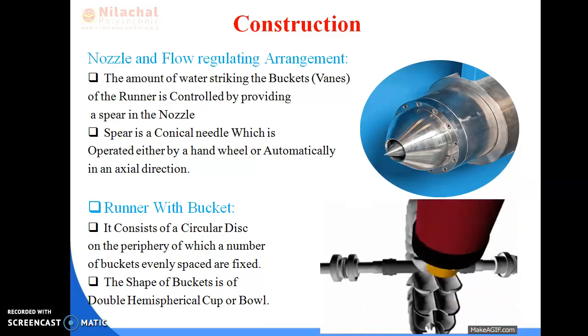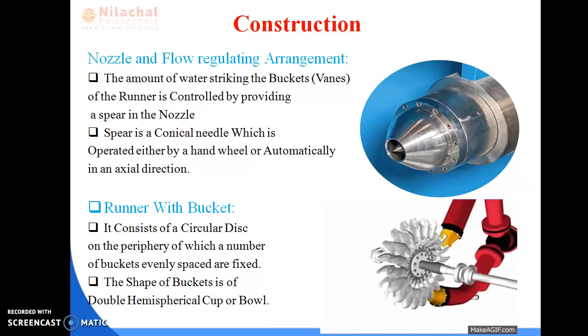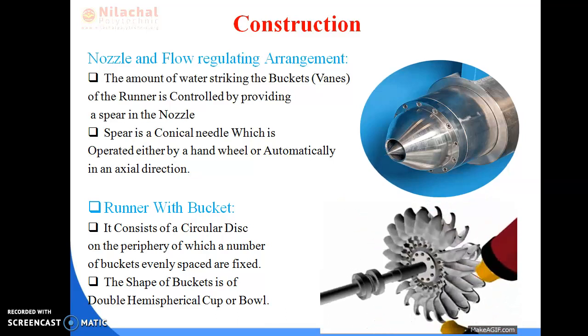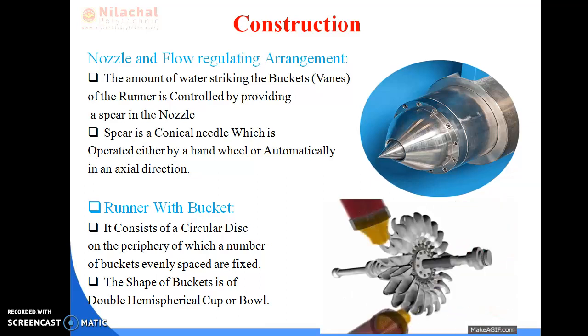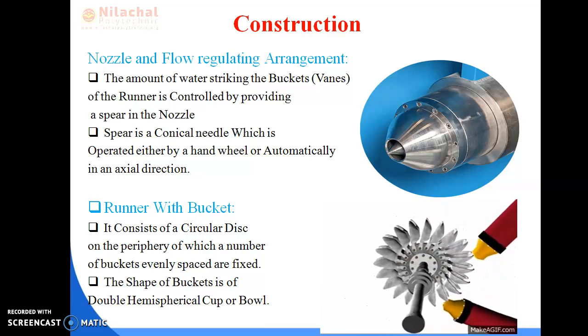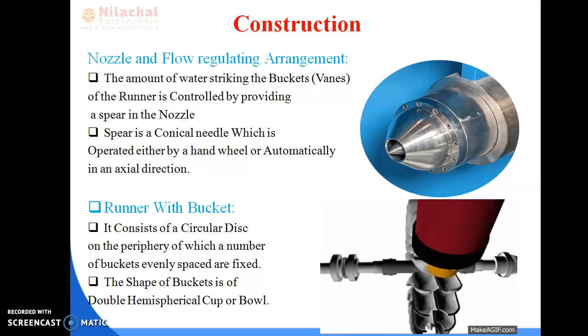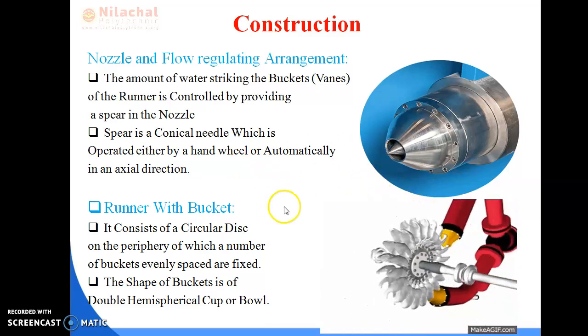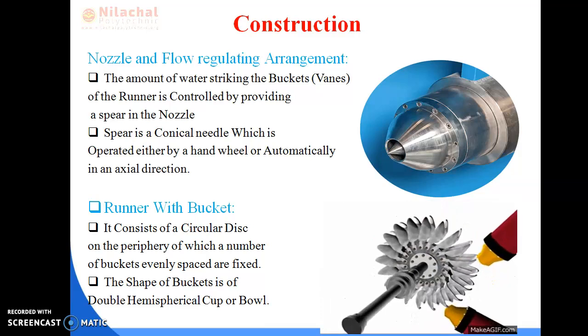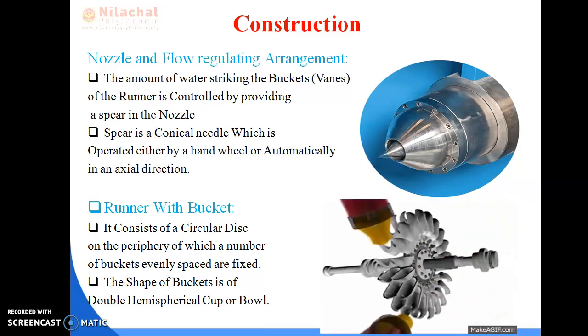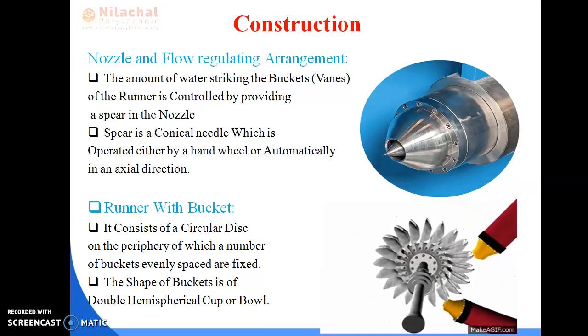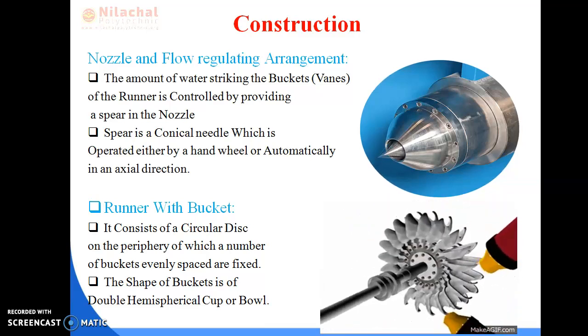The mass of water can be regulated using the spear arrangement. While the spear is moving towards the front end in a forward motion, the liquid flow will be decreased and less amount of water will be discharged. While it is moving inward, a larger amount of water will be provided to the turbine unit. In this way, the flow is regulated by the spear. The main purpose of the flow regulating arrangement is to supply water depending upon the load at the output shaft of the turbine unit.